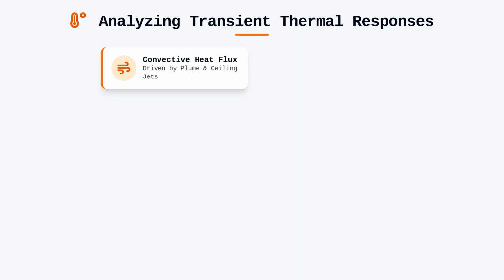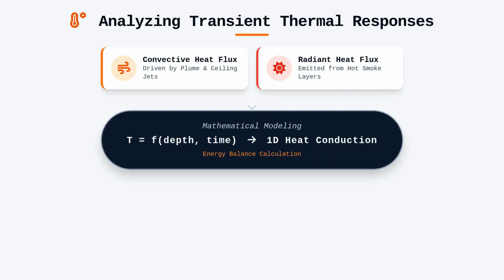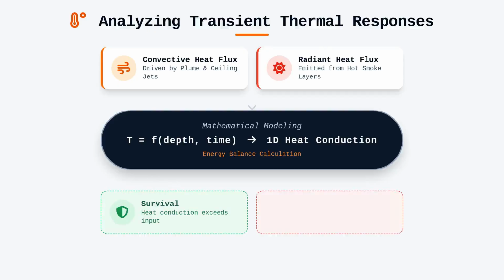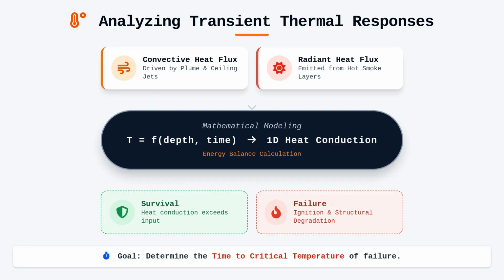We must account for the convective heat flux from the plume or ceiling jet and the radiant flux from the hot smoke layer. When we perform these energy balance calculations, we are essentially building a mathematical model of survival versus failure. If the energy input through radiation and convection exceeds the material's capacity to conduct that heat away, we observe a temperature rise that can culminate in ignition or structural degradation.